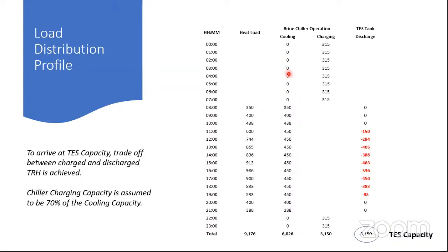Because in chilled water, my chiller could charge and cool simultaneously. But in ice thermal storage, my chiller's charging temperature is different and cooling temperature is different. So I really need to have some charging hours that are empty, that are available for the chiller to charge the thermal storage tank at night. That's the reason for selecting a base load chiller in such cases. So 3150 is the TES capacity. When we sum up this discharge pattern, this is our thermal energy storage capacity. This is what it works out to be.